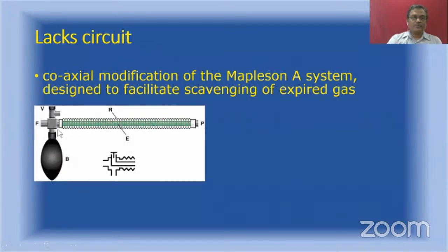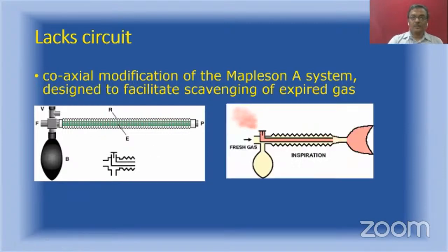Look at this picture. This is a coaxial circuit. There is an inner tube, there is an outer tube. But unlike the Bain circuit, the inner tube is carrying the expired gas from the patient. You can see it is carrying expired gas towards the valve. Look at this picture. Expired gas is inside the inner tube, which is going out through the APL valve. And the outer tube, unlike the Bain circuit, here the outer tube carries the fresh gas towards the patient. See, expired gas is moving through the inner tube and going out, while the outer tube is carrying the fresh gas.